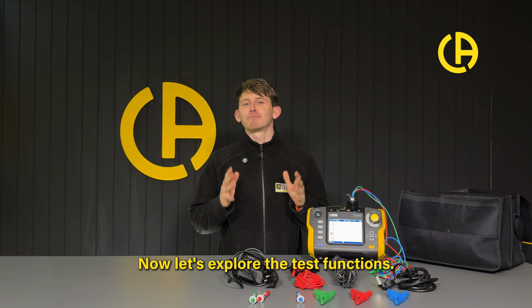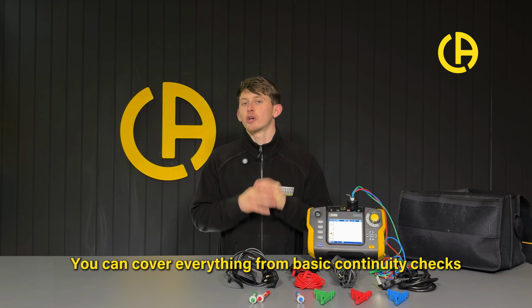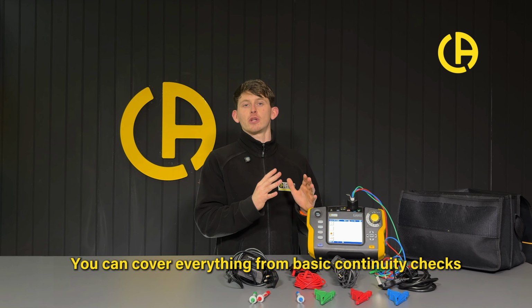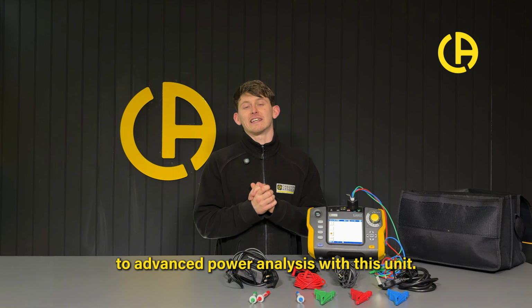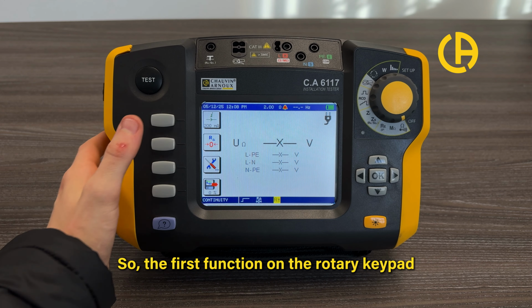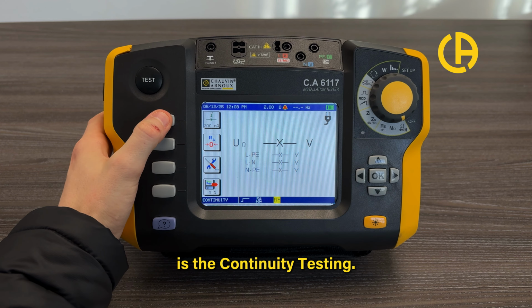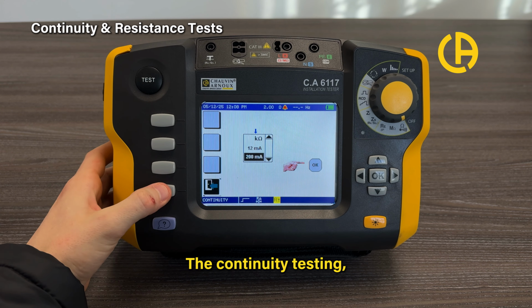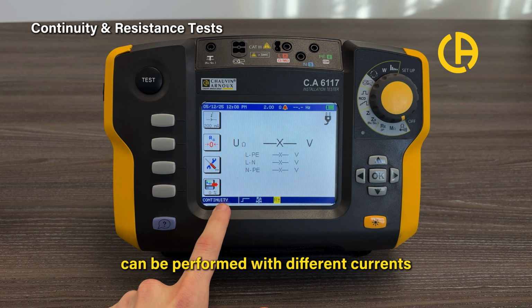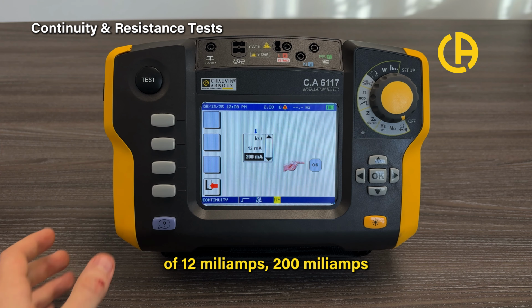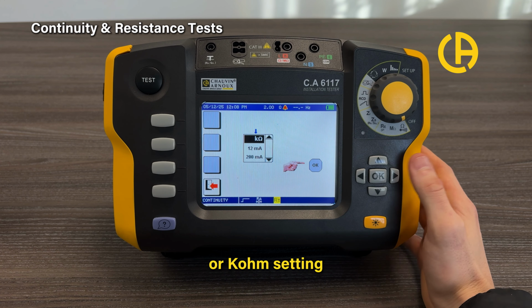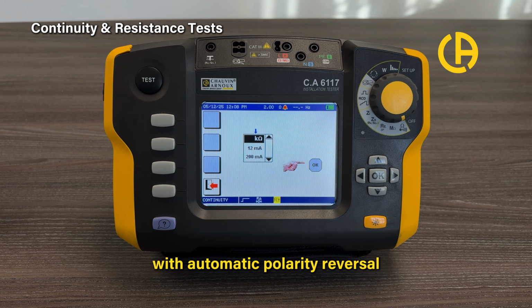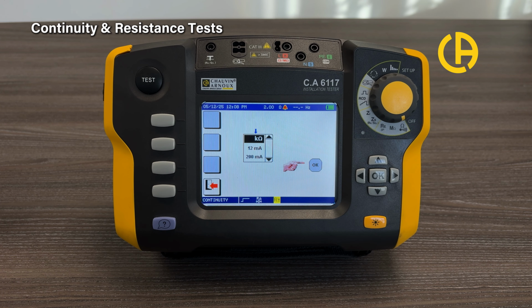Now, let's explore the test functions. You can cover everything from basic continuity checks to advanced power analysis with this unit. So the first function on the rotary keypad is the continuity testing. The continuity testing can be performed with different currents of 12 milliamps, 200 milliamps or a kiloohm setting, with automatic polarity reversal for verifying protective conductors.